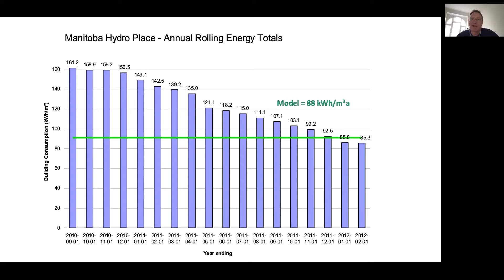So what you see here is the energy consumption the first month, September 2010, when we had a full year of operation, and then October 2010, November 2010, and so on, always looking at the previous year. We had some hydronic issues, which got fixed here, but it was not a single major problem. There was this one hydronic problem, but it's a couple of hundred of small items. A sensor which is not sensing a correct temperature, a control routine which is a little weird, these kinds of things, and you have to find them and fix them before you reach the number we had predicted or projected in design.